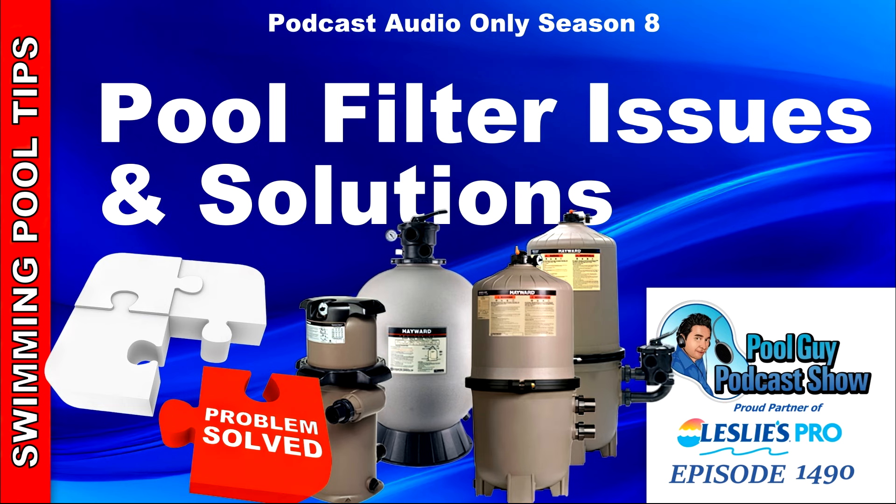DE filters have to be backwashed on occasion. When you backwash a DE filter, not all the DE comes off the grid. I always like to put two or three pounds back in depending on the DE filter size, or about half of the DE I originally used, especially if doing about a two-minute backwash. I have videos on my channel that focus on backwashing and how much DE to add back — I would refer to those rather than here because those go into a lot more detail.